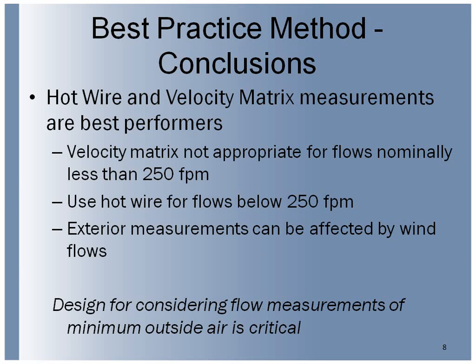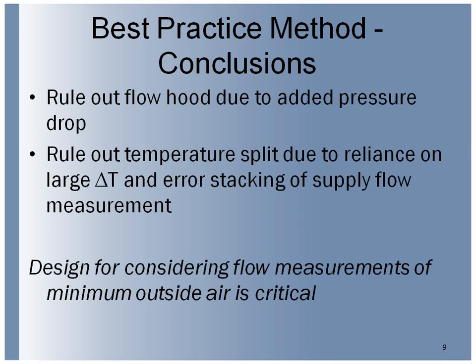So one of the key takeaways from this is design, and I'll come back to this, but just to seed the thought for us designers, designing for consideration of how this outside air minimum flow is going to be controlled and tested is really critical. And we'll talk a little more about that. We didn't use a flow compensated hood or pressure compensated hood. So flow hood was out for a variety of reasons, obviously. And temperature split really has error stacking problems, and you have to have some absolute reference for measurement to make that work.